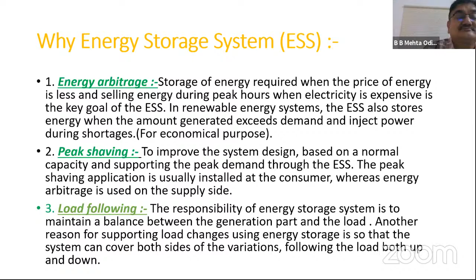It also acts as a spinning reserve. As per the IEGC mandate, 50% capacity of the highest operated plant should be online as hot spinning reserve available with the dispatcher. In case of regional load dispatch, 100% capacity of the largest unit in the region should be the on-bar spinning reserve. This also acts as a spinning reserve because restoration of power from the stored device is very fast, immediate, and can be deployed at any moment.